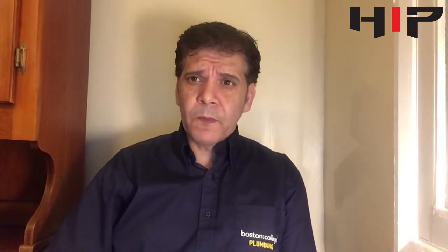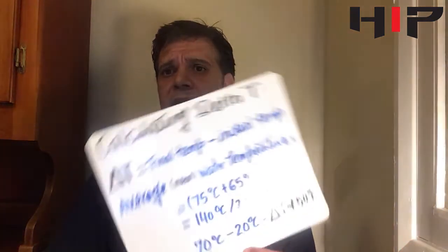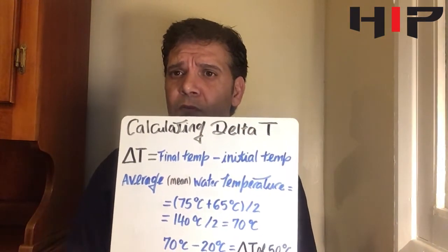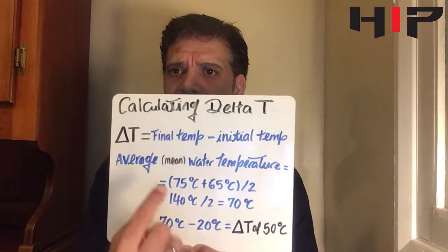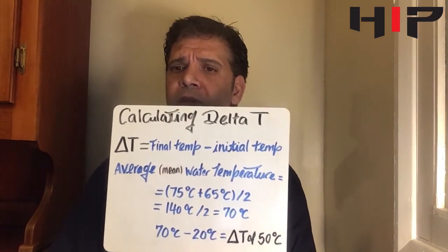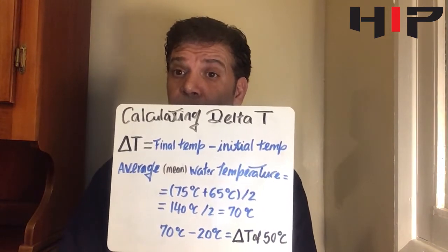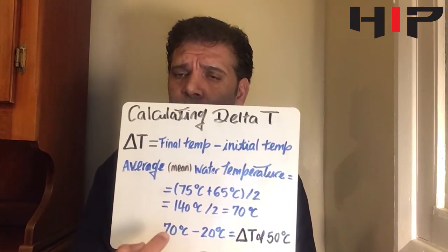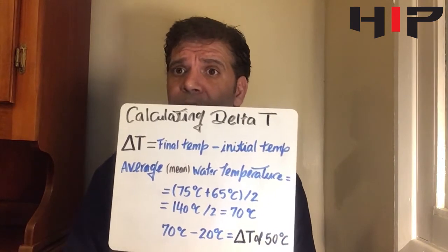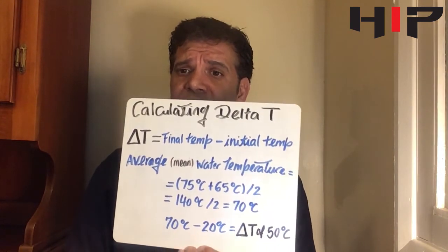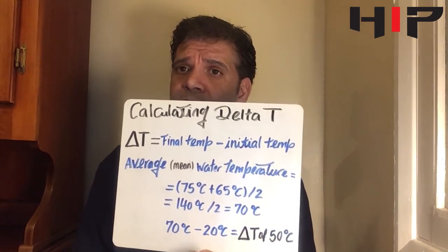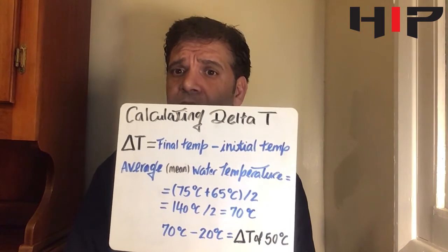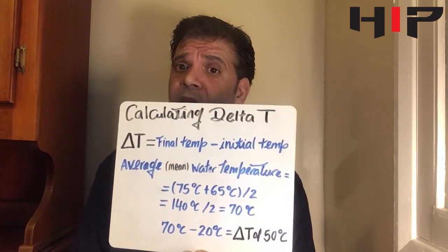Delta T is a difference between the average water temperature and the ambient air temperature. To calculate delta T — that is the symbol — we need to find the average, taking the final and initial temperatures. So your flow temperature is 75 degrees; adding 75 to 65 degrees, which is your return, gives you 140 degrees. Divide that by 2, it gives you 70 degrees. You then take 20 degrees, your consistent air temperature, from 70, which gives you a final delta T average of 50 degrees. This is how you calculate delta T.